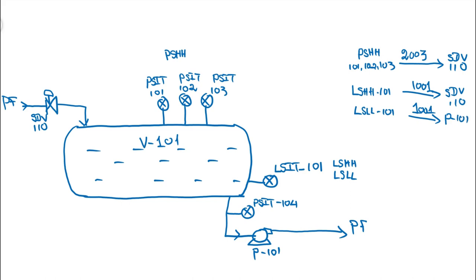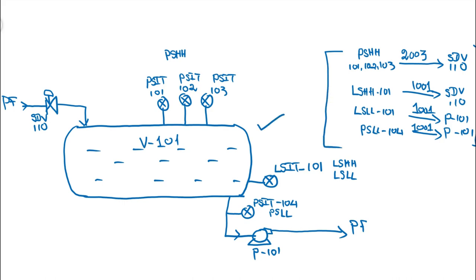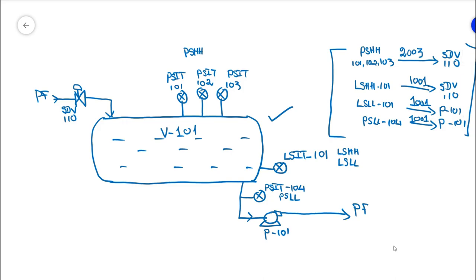PSIT-104 on the suction line has a pressure low-low trip. On a one-out-of-one logic, it trips pump P-101 to protect it from damage. These are the trip initiators for protecting the vessel. Now let's capture this control philosophy in the cause and effect sheet.